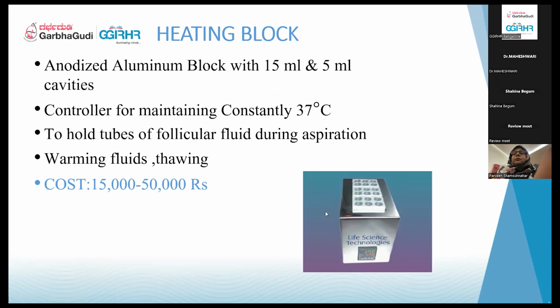Into these, you can see these columns over here. These are the locations, the points where we place the Falcon test tubes, which will be used to aspirate, where the aspirated fluid gets collected. That will be placed inside that. So the test tubes are warmed at 37 degrees. You need to maintain the temperature during the entire course of the procedure at 37 degrees. That is why the test tubes are placed here. So this should be switched on and maintained at 37 degrees.